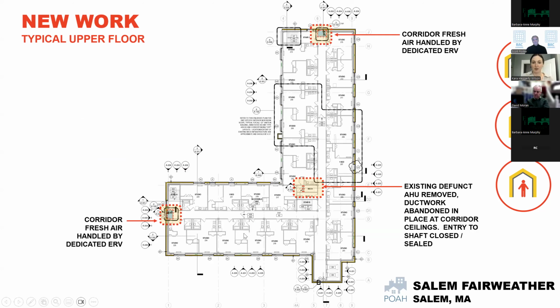So the typical upper floor - it's 6 stories, so floors 2 through 6 are essentially duplicates. The real work is at the end of the corridor, where we're adding corridor-specific ERVs. Those ERVs aren't tied into the rest of the building, partly because the building's fire alarm system cannot support installation of smoke dampers.